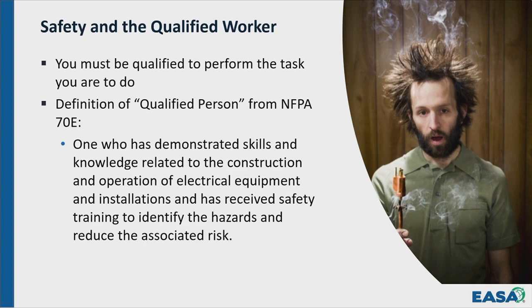This becomes apparent, or even more important, in medium voltage systems. You don't want a guy or gal walking up to a 2300 volt or 4160 volt contactor to figure out why something won't start, taking a wiggy or a fluke and putting it across a medium voltage fuse to measure voltage or see if it's open, without understanding that's medium voltage equipment.